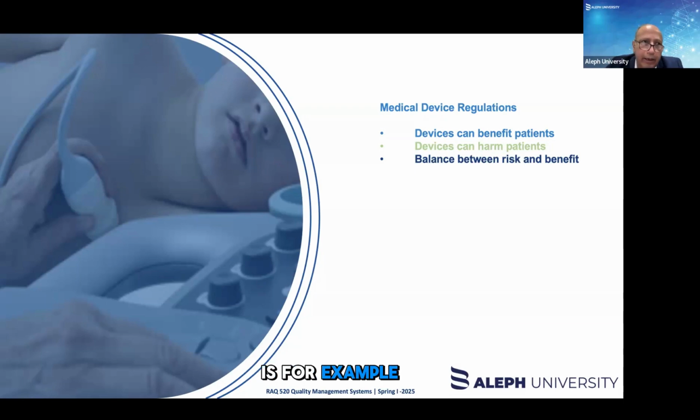For example, if you have an ultrasound system used for obstetrics and gynecology, and they're checking the gestational age of a fetus, and the calipers to measure the head circumference are bad or incorrect, then the gestational age of the fetus is going to be incorrect, and therefore any type of diagnosis is going to be incorrect.